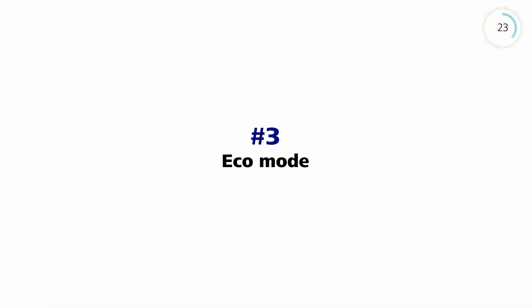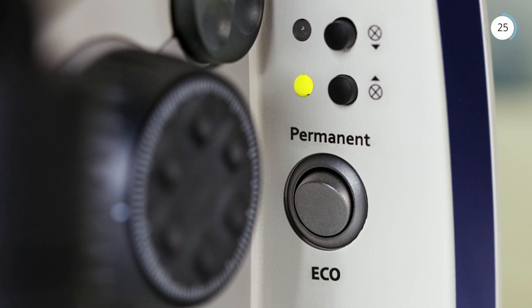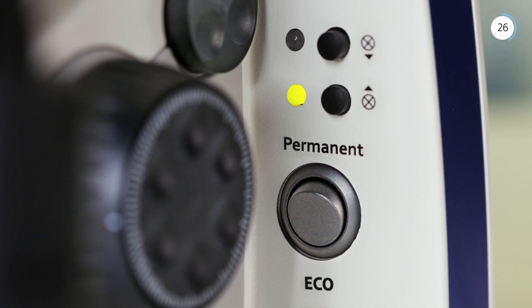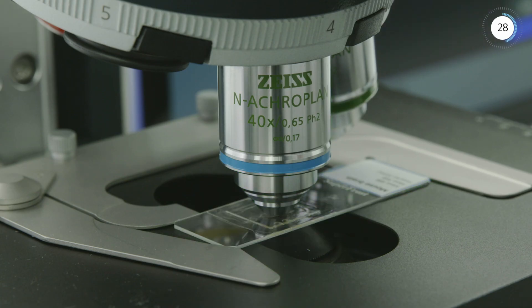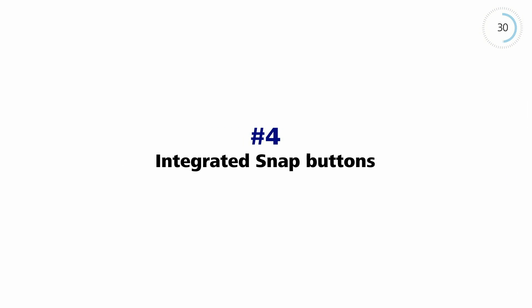Axioscope 5 goes to standby after being idle for 15 minutes. This saves energy and extends the lifetime of the illumination.